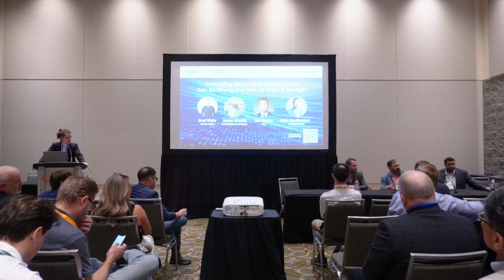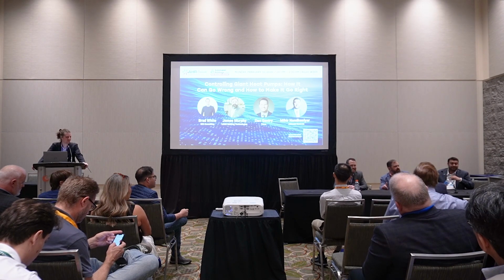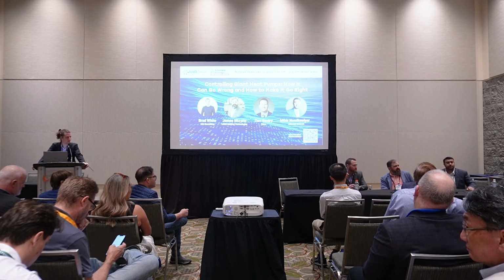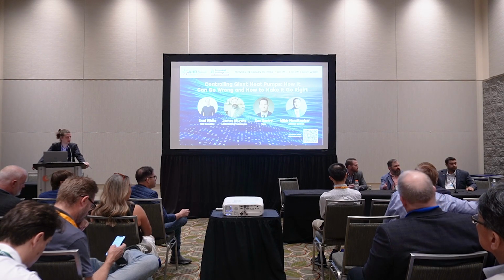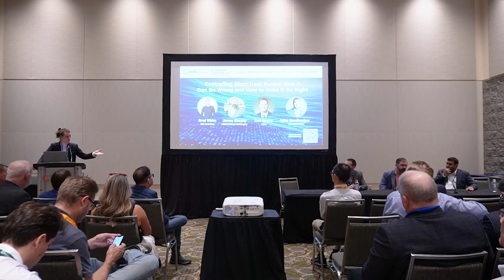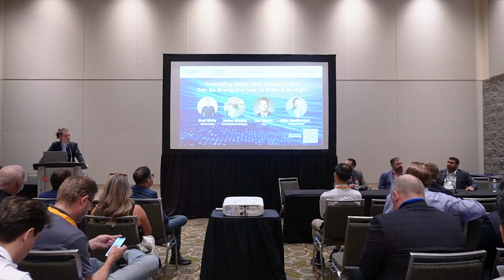I think it's more about the gallons, or liters for our Canadian friends, that are available in the system. Then you might not need as big a buffer tank. Maybe you could get away with a 500. So it is definitely a volume calculation, and it has to be the volume available to the device, right? If it's valved off, you can't count that volume. If it's hydronically isolated in a different loop, it's no good. But that's part of our design process. We talk to the manufacturer about the minimum system volume, and then we look at the pipe lengths and the diameters, and okay, we need 1,000 gallons, 500 gallons, whatever. That is part of the process for sure.